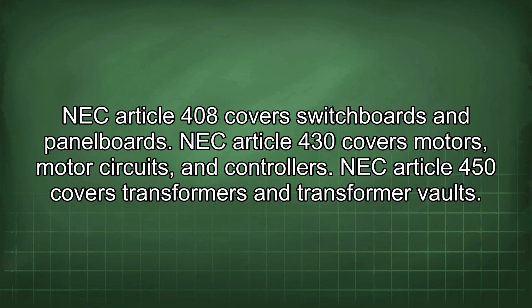NEC Article 400 covers flexible cords and cables. NEC Article 408 covers switchboards and panel boards. NEC Article 430 covers motors, motor circuits, and controllers. NEC Article 450 covers transformers and transformer vaults. NEC Article 500 covers hazardous locations.